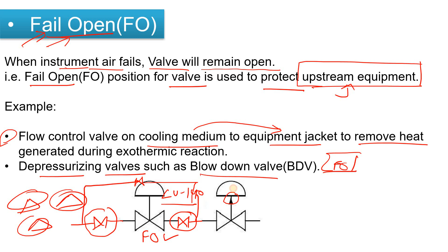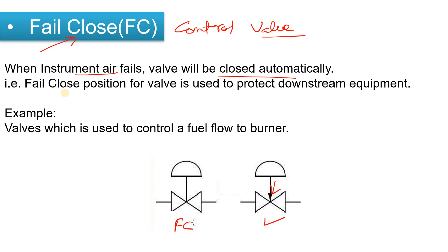Now the another condition is fail to close, the fail to close control valve. For this type of control valve, in the P&ID there will be written FC, and another symbol could be like that. Let's suppose the signal is going into the control valve. Same here, in that case it means that whenever the instrument air or driving force fails, your valve will be closed. So in this case, whenever the instrument air fails, your valve will be closed automatically, right?